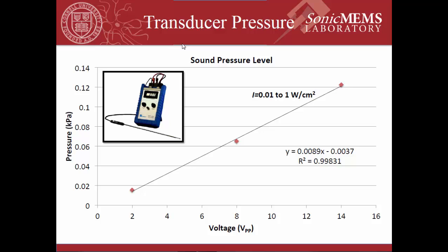So the sound pressure levels were also measured, and at the 3 different voltages, you see that it's pretty linear with respect to the applied voltage. We're getting around 20 to 120 pascals of pressure and 0.01 to 1 watts per centimeter squared of intensity for the different voltages. And the image at the top left is the hydrophone that we're using to acquire this data.